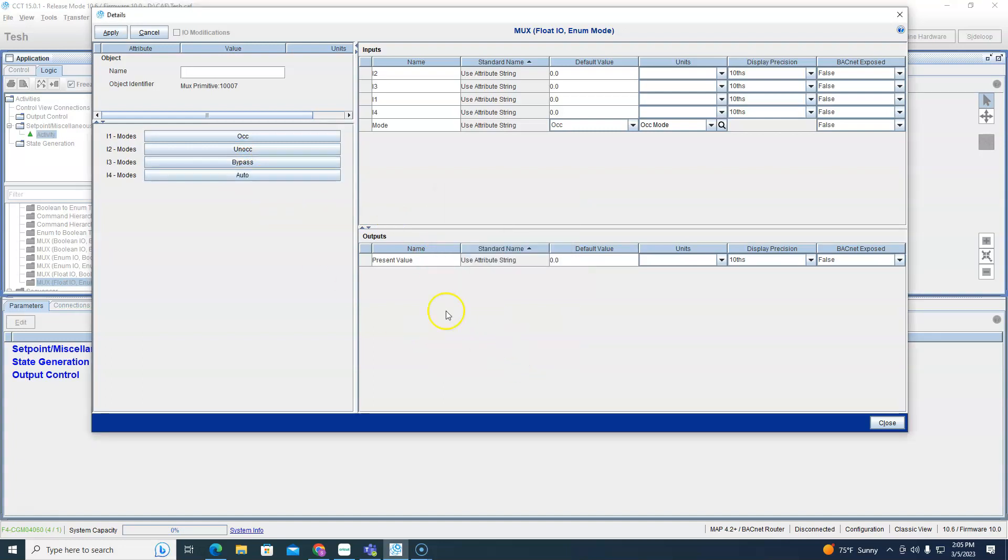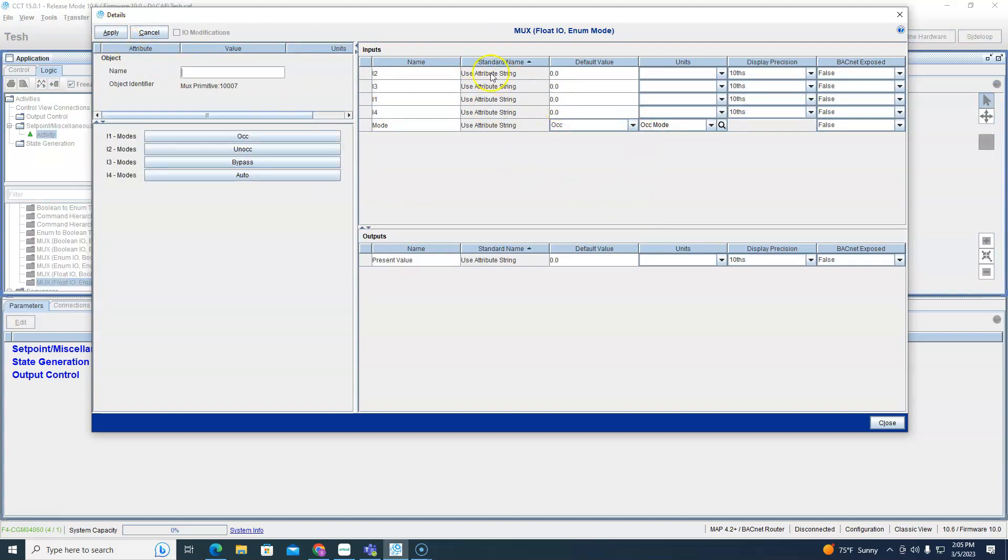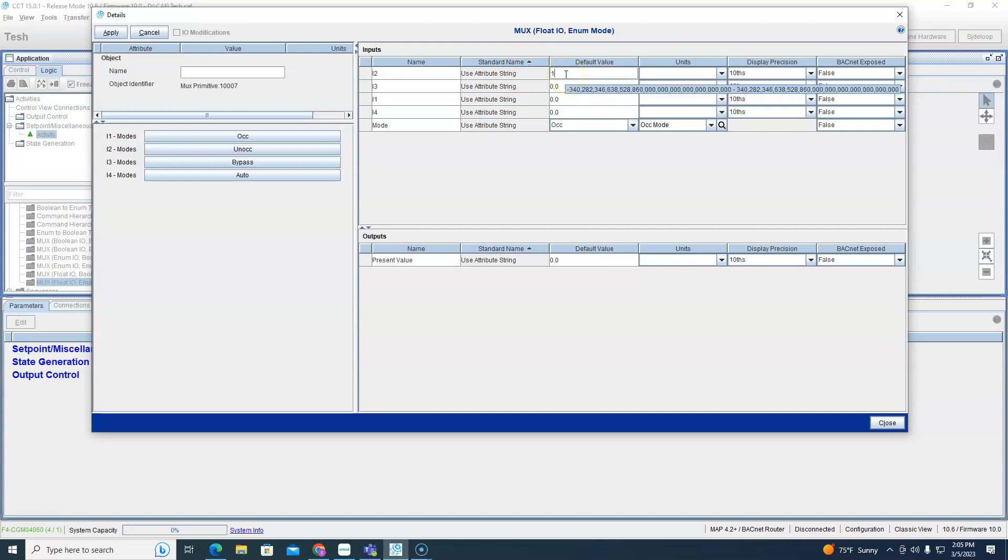So let me show you. Maybe mode one we want occupied, mode two unoccupied, something in bypass, and something in auto. Okay, boom. So now one is going to be occupied, two is going to be unoccupied, three is going to be bypass, and four is going to be auto.